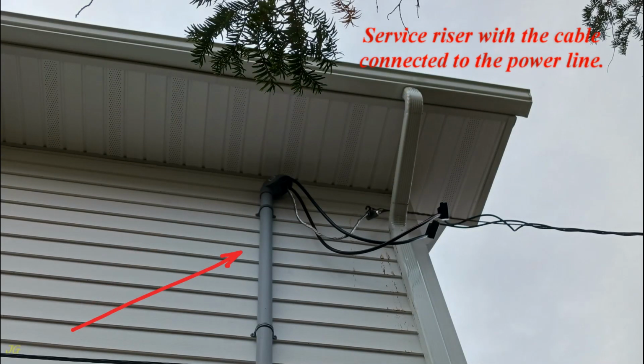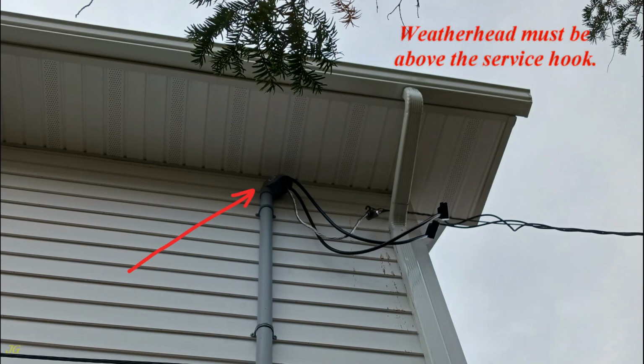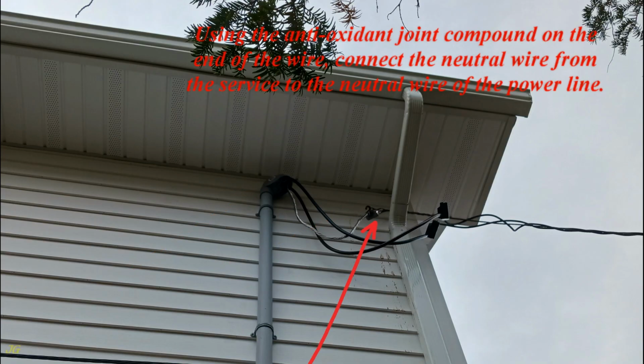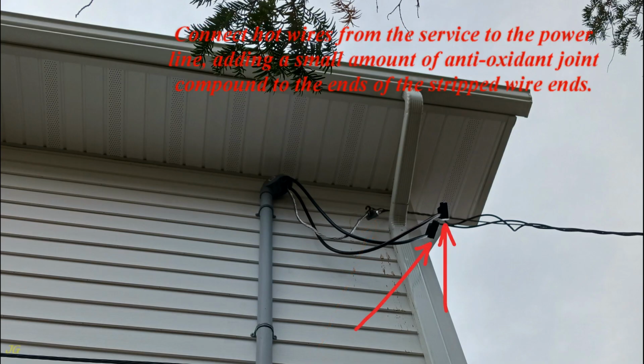Service riser with the cable connected to the power line. Weatherhead must be above the service hook. Using the antioxidant joint compound on the end of the wire, connect the neutral wire from the service to the neutral wire of the power line. Connect hot wires from the service to the power line, adding a small amount of antioxidant joint compound to the stripped wire ends.